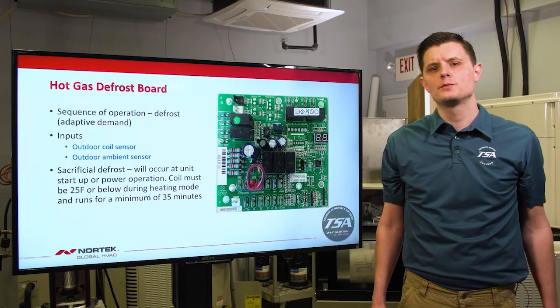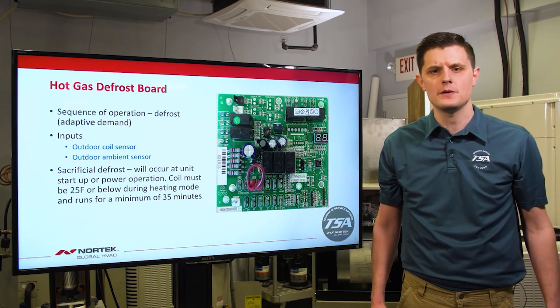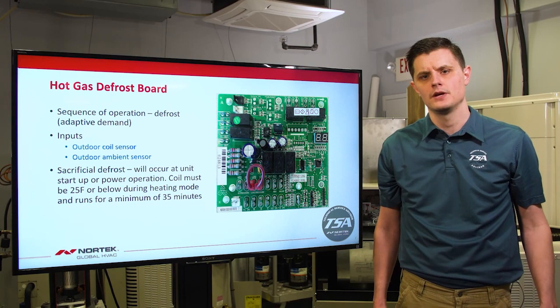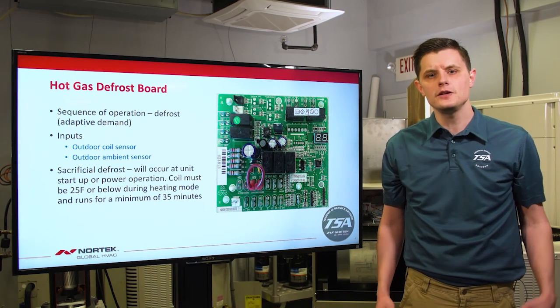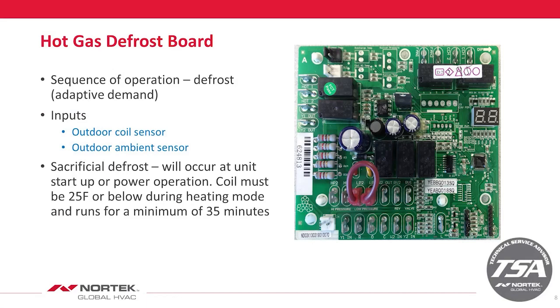This adaptive demand defrost board takes into account your outdoor ambient temperature and the coil temperature to calculate when the unit should go into defrost mode. These inputs come from the outdoor coil sensor and the ambient sensor on your defrost board. A sacrificial defrost will occur at unit startup or power operation. The coil must be 25 degrees or below during heating mode and the unit must run for a minimum of 35 minutes.